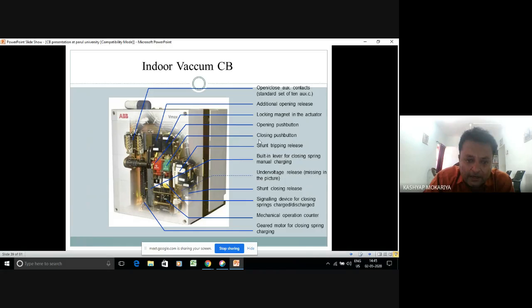Now you can see here the closing push button. You can see the shunt trip release. We have two types of releases. A shunt trip release is there. The under voltage release is there. Under voltage release operates on 70% or 80% of the voltage level. Then we have a locking magnet here. We have this spring. You can show.